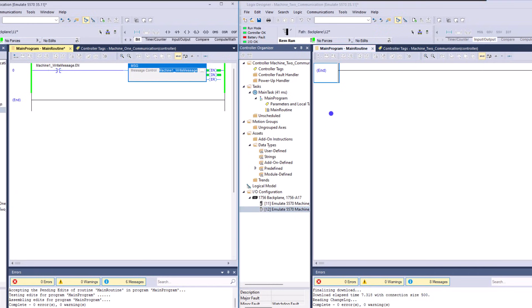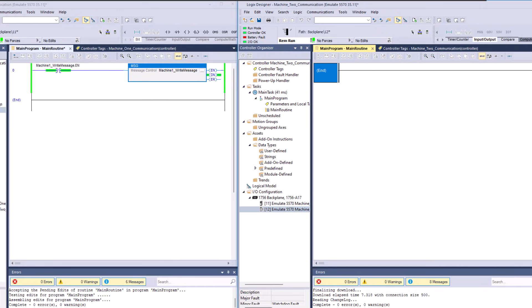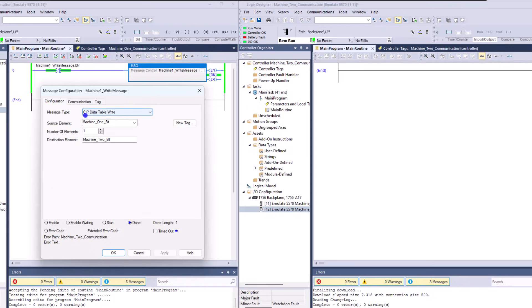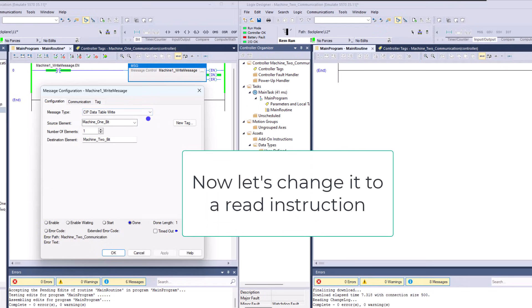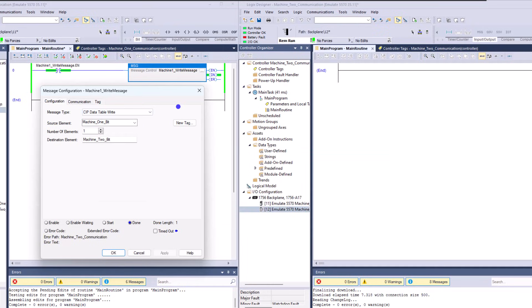We could do a read similarly - we would just do everything in reverse, with everything on machine two. Don't think that if you're using a message instruction you need to have both a read and a write - you just need to have one. That's something that confuses people at the beginning of learning message instructions. There are some complex things you can do with messaging, but this is a very simple illustration. The setup I've shown you is a CIP data table write.